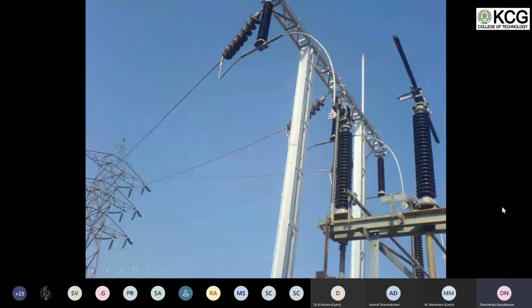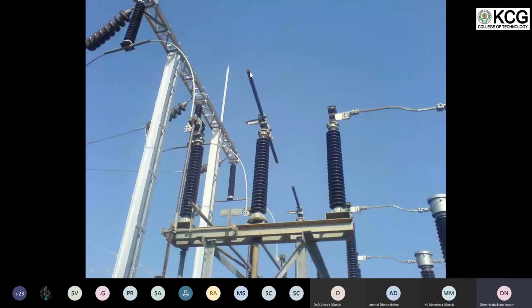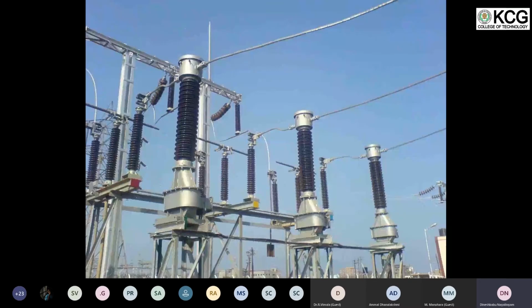This is the isolator. Earlier I was telling a story about the movement of the isolator taking 15 to 20 seconds. This rotates, and this end gets into this arm. So the movement time is 15 to 20 seconds. It moves into a CT, current transformer. You can see here these isolators are yellow and blue phase, red, yellow, blue. And the CT is easy to identify. The CT is in series. You can see here the transmission line is broken. It enters into one equipment and moves out. And the secondary will be here through cables. CT secondary. So this is the CT primary.